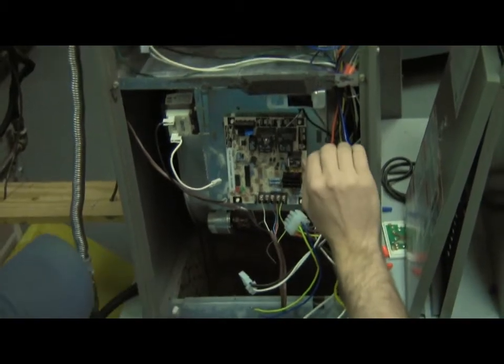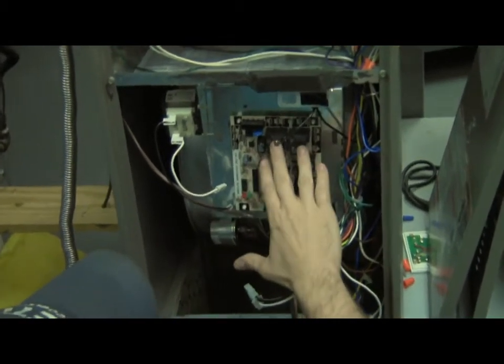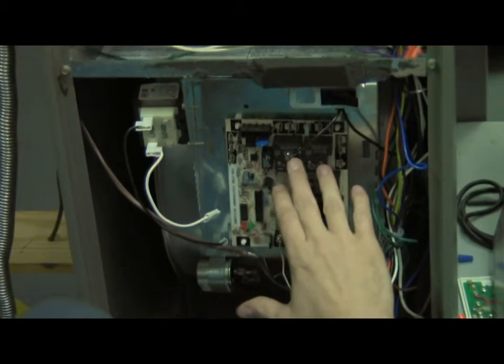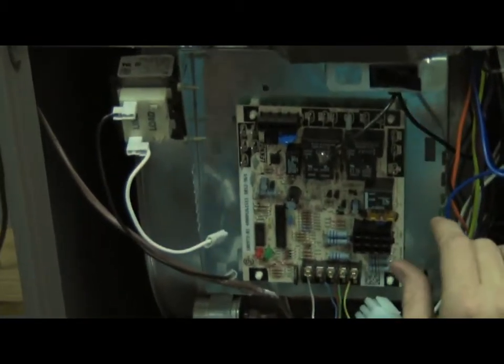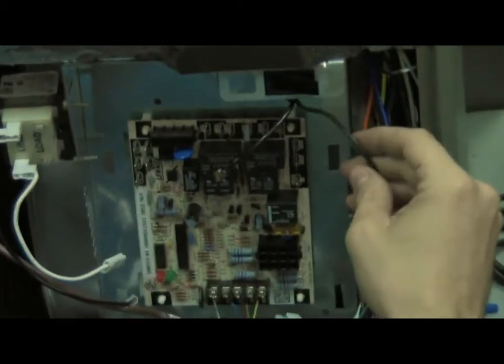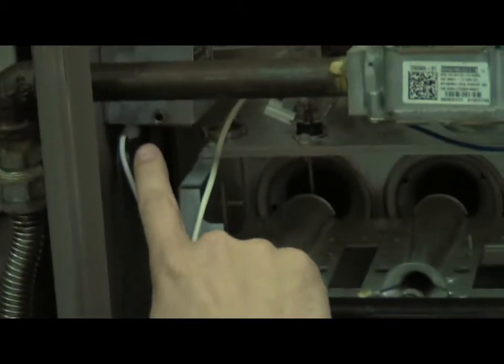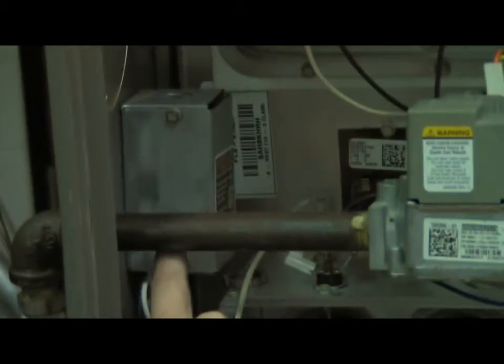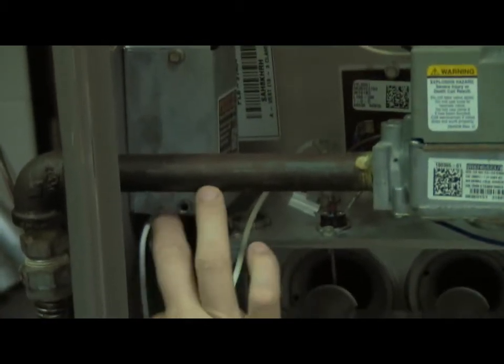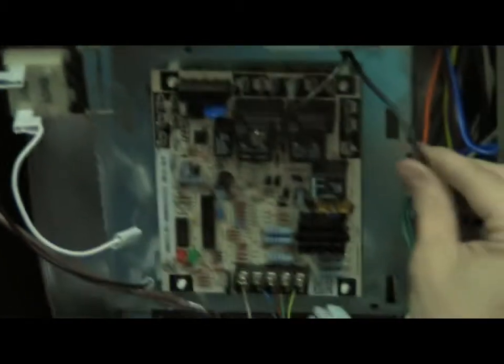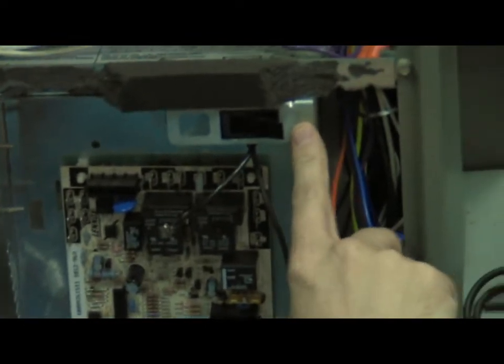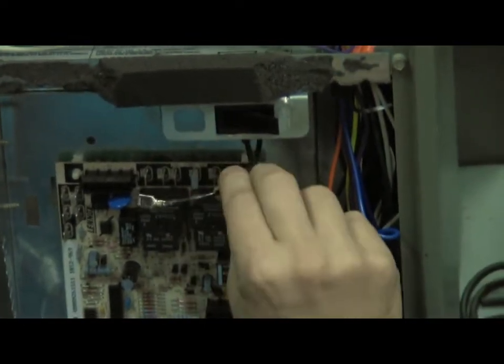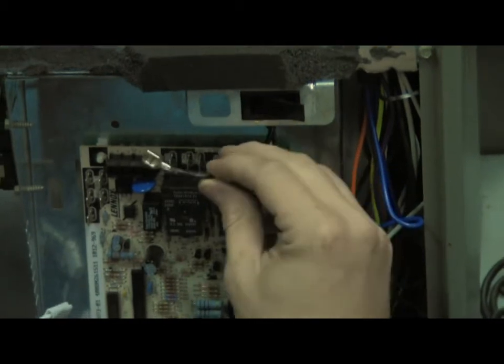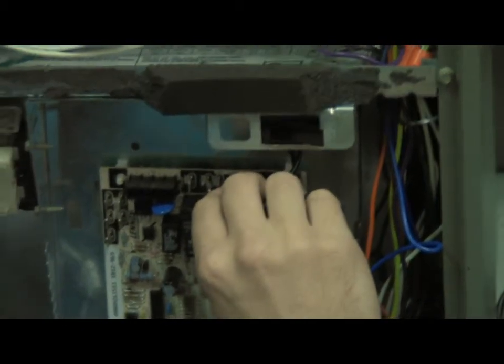Alright, in order to wire this control board, I'm going to start with the high voltage first. This black wire here is 120 volts that comes from your supply box. There's a 120 volt black and your white neutral. Okay, 120 volt black goes to the door switch. From the door switch, it needs to supply 120 volts to the control board to the line terminal.